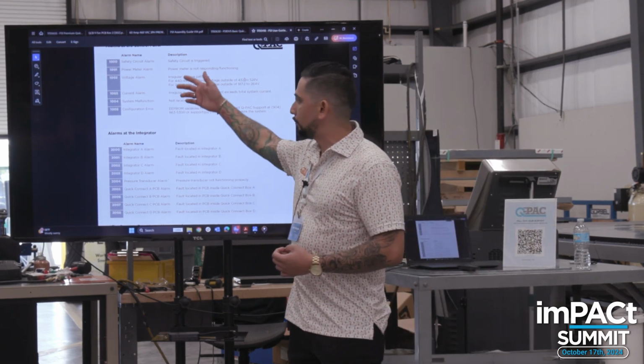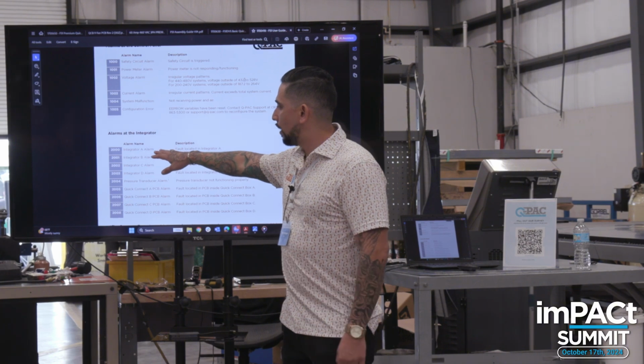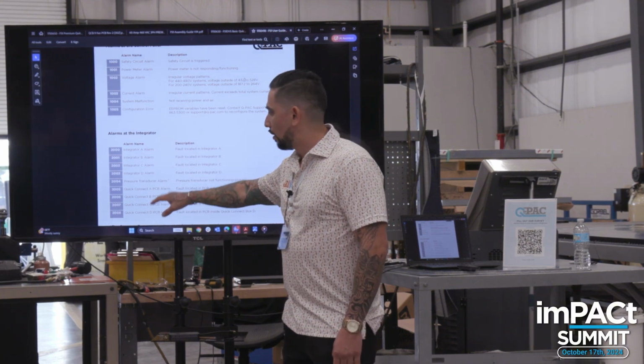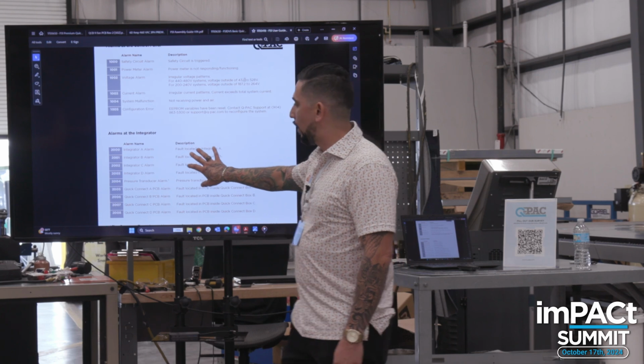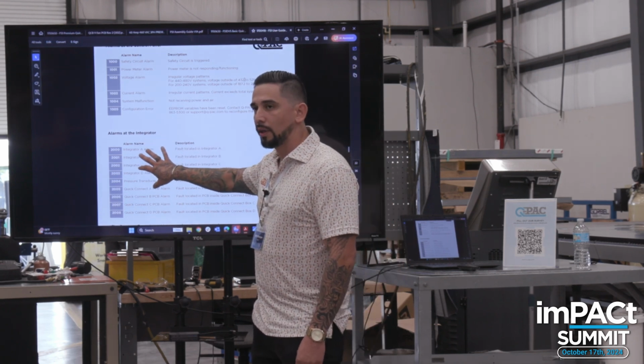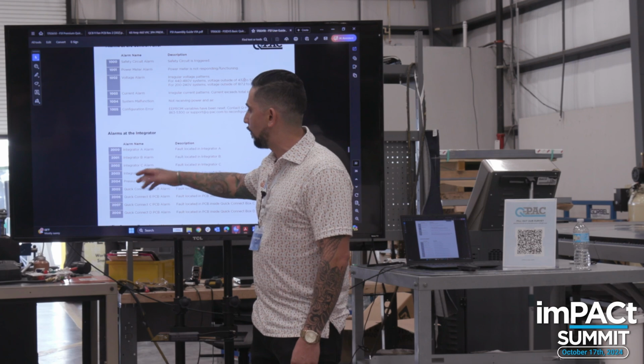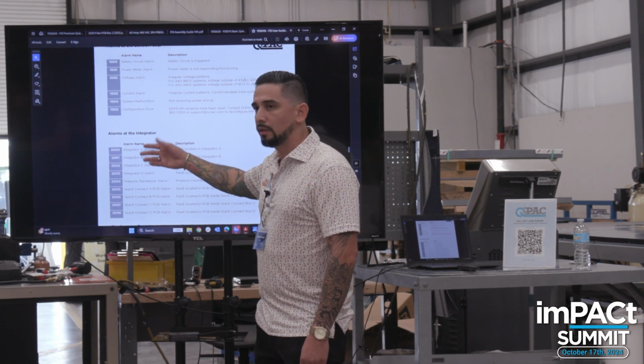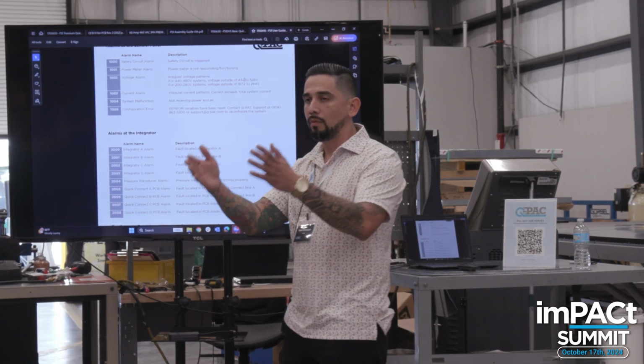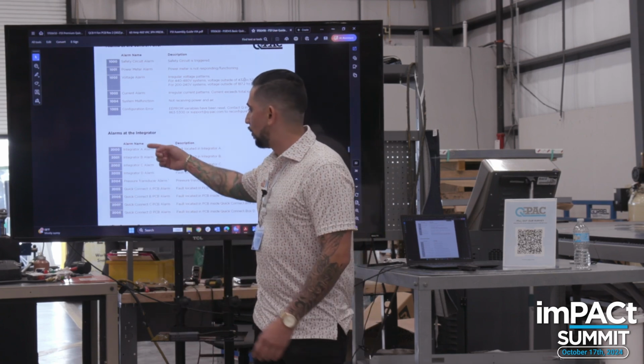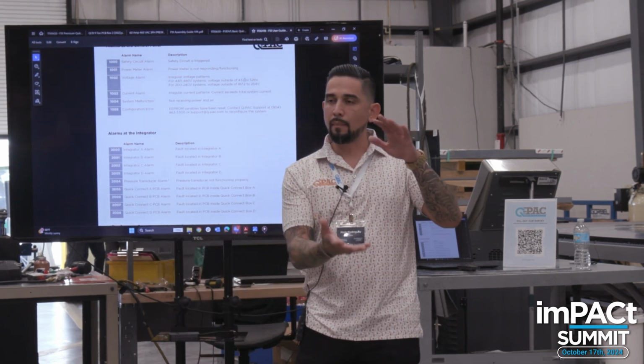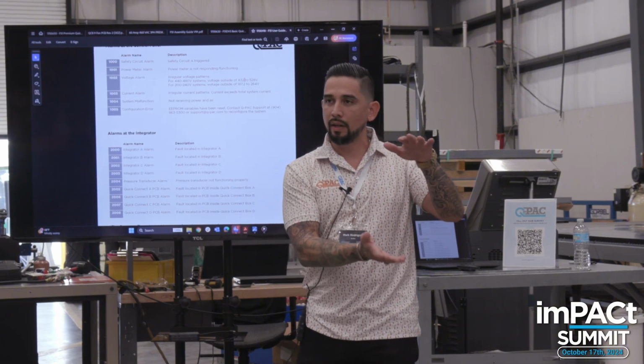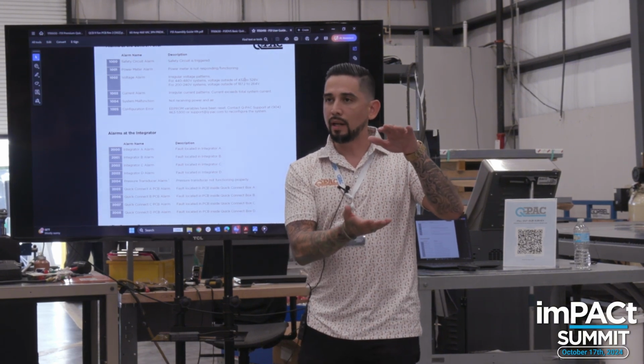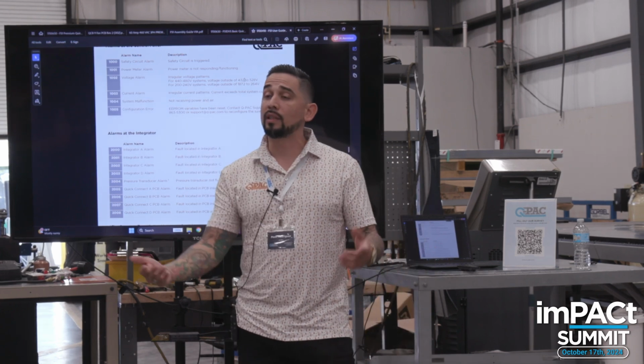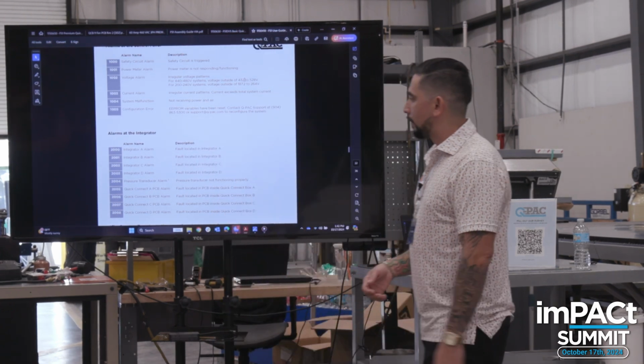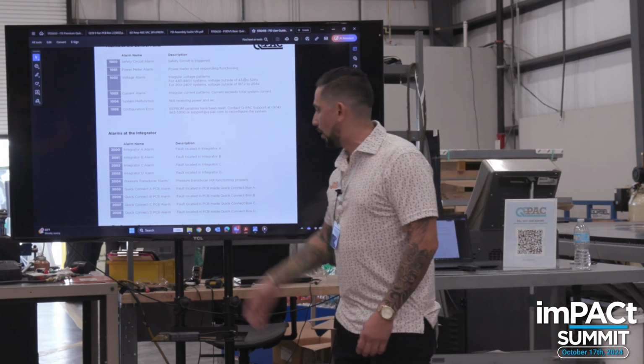So you have all these different alarms. 2000s are integrator alarms. There's a lot here, but they're very simple to understand. Once you understand that your integrator and your quick connect box are one and the same. These are just different quick connect boxes if you had multiple fans in your system. So if you get an integrator A alarm, that means that box that has all these motors connected to it, integrator A, QCB A, has an alarm. That means there's a fan down or a motor down, or it's not getting the feedback that it needs. So that will trigger one of these integrator A alarms.